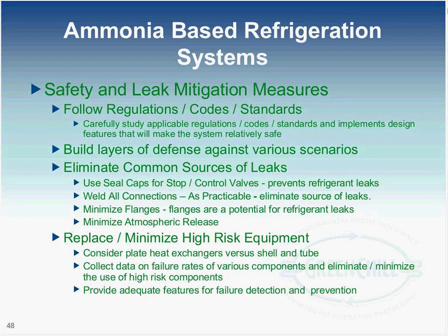You would like to eliminate the common sources of leaks that would happen in a system, especially an ammonia system. You want to use stop valves and control valves with seal caps to prevent leaks. You would like to use welded connections instead of flanges. That would eliminate sources of leaks. And always use certified welders. Use nondestructive examination techniques and seamless pipe for minimizing leaks. Although flanges are unavoidable in certain serviceable components, try to minimize them.